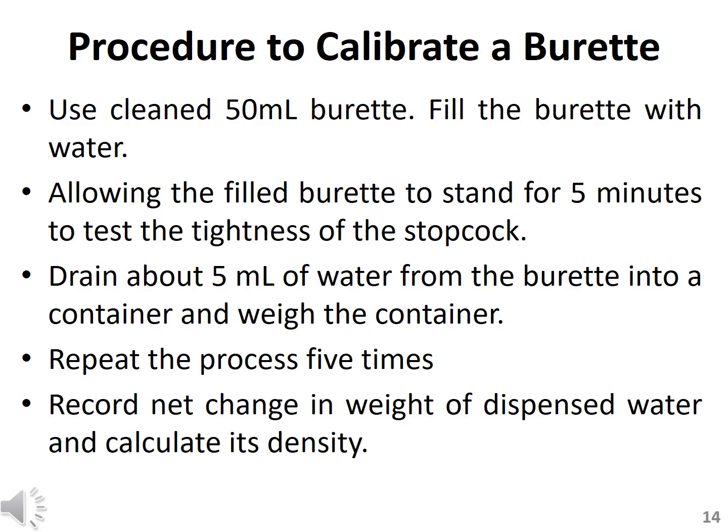So we will repeat this process 5 times with the same volume, 5 ml of water, and you can repeat this process for 10 ml or 20 ml volumes as well. Then after getting the net weight of the water, we will calculate the density of the water at the specific temperature in the laboratory, for the water which is being used.